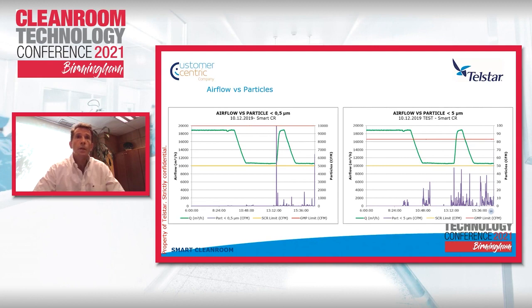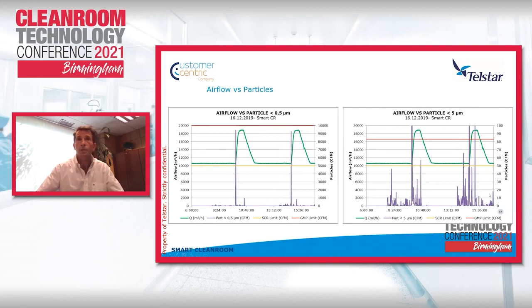That test was also made with a different concentration of 5 micron particles, and the system did not react because we never reached the yellow line. The system reacted because at 0.5 microns it was above the yellow one. We made the same test with a different concentration of the biggest particles, and here it was a bit longer to recover, but we are still talking about 2 to 3 minutes to recover the situation.